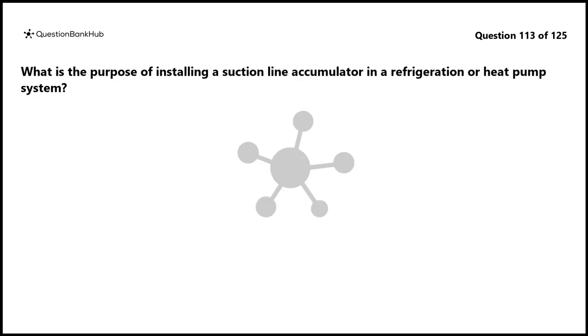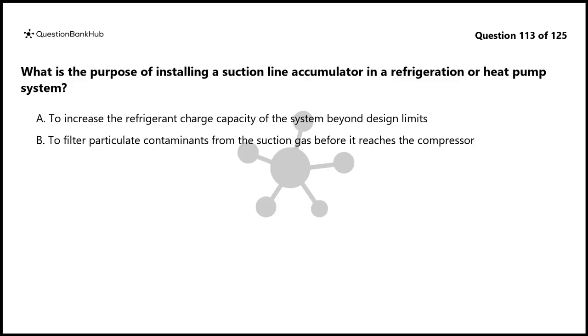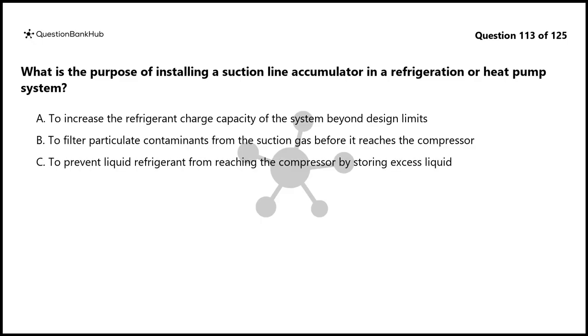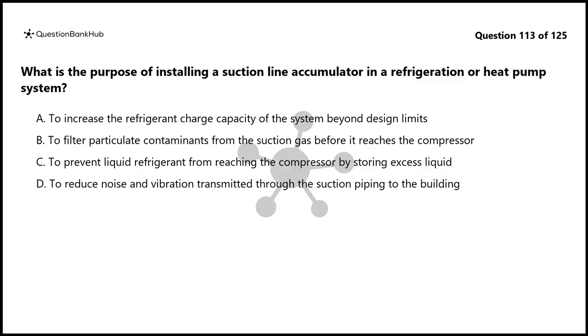Question 113. What is the purpose of installing a suction line accumulator in a refrigeration or heat pump system? A. To increase the refrigerant charge capacity of the system beyond design limits. B. To filter particulate contaminants from the suction gas before it reaches the compressor. C. To prevent liquid refrigerant from reaching the compressor by storing excess liquid. D. To reduce noise and vibration transmitted through the suction piping to the building.